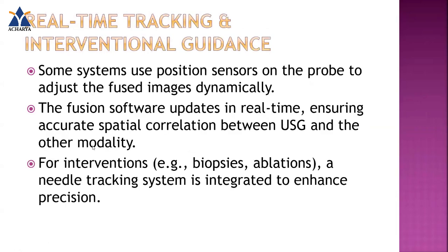Real-time tracking and interventional guidance. Some of the systems use a positioning sensor on the probe that adjusts the fused image dynamically. The fusion software updates in real time, ensuring accurate spatial correlation between the ultrasound and the other modality.